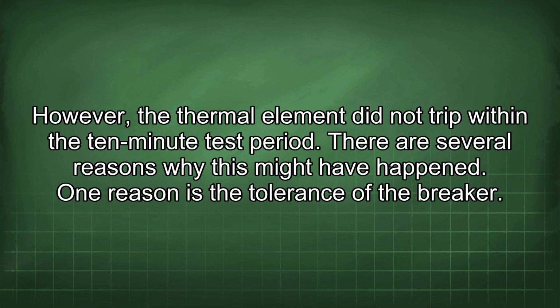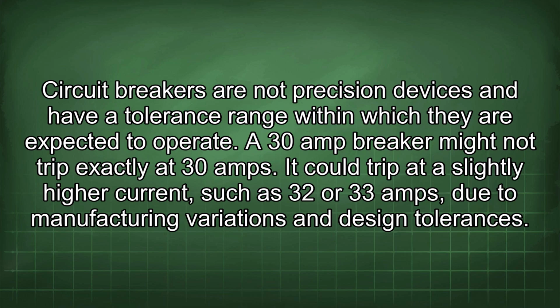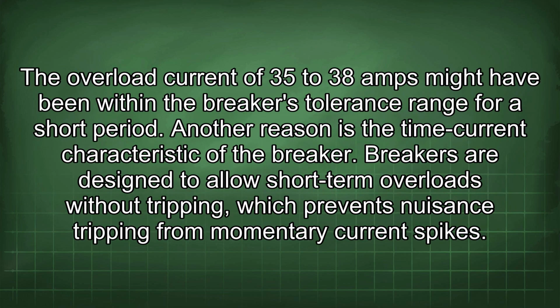One reason is the tolerance of the breaker. Circuit breakers are not precision devices and have a tolerance range within which they are expected to operate. A 30 amp breaker might not trip exactly at 30 amps. It could trip at a slightly higher current, such as 32 or 33 amps, due to manufacturing variations and design tolerances. The overload current of 35 to 38 amps might have been within the breaker's tolerance range for a short period. Another reason is the time current characteristic of the breaker.